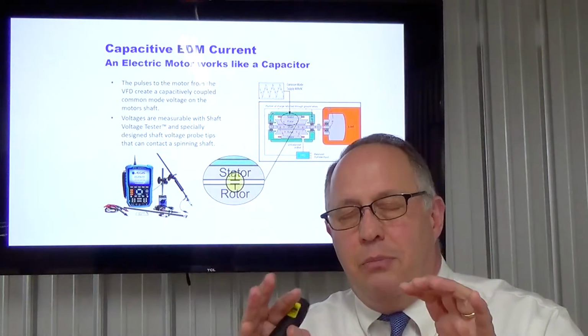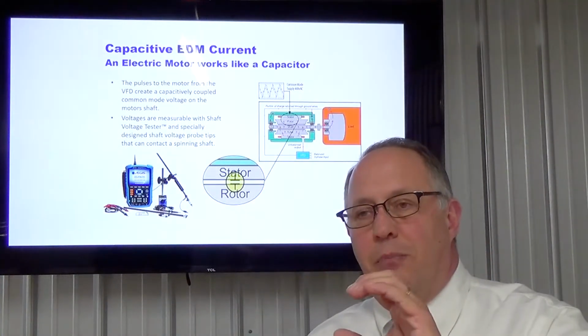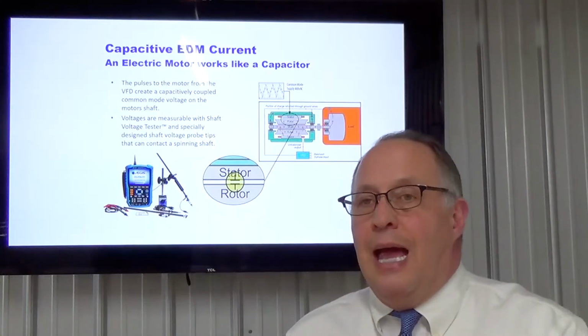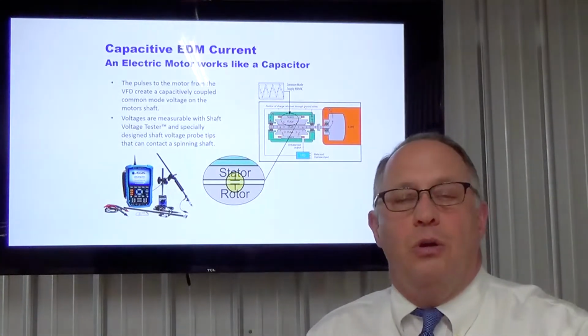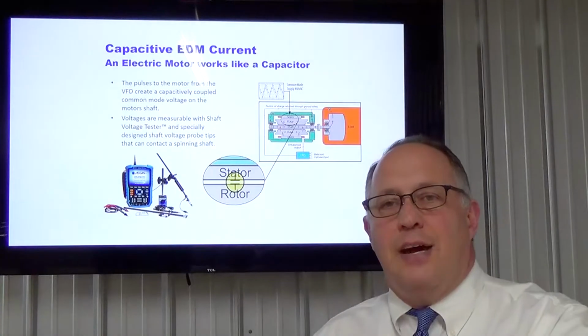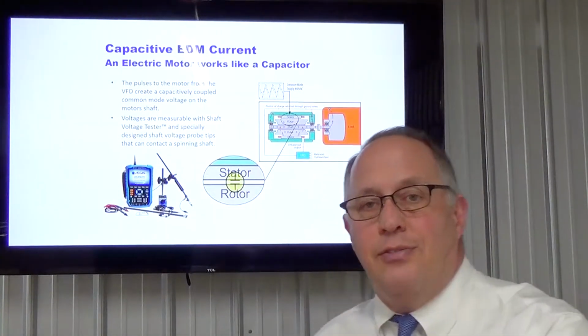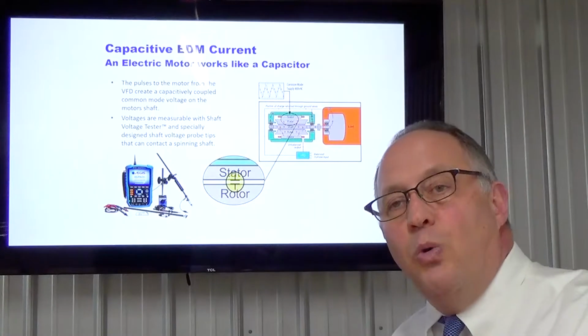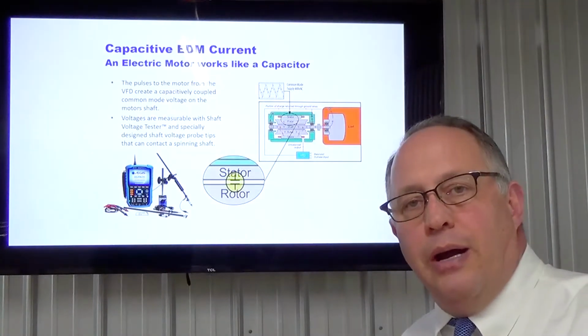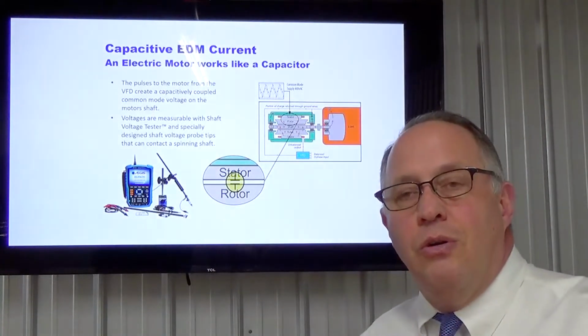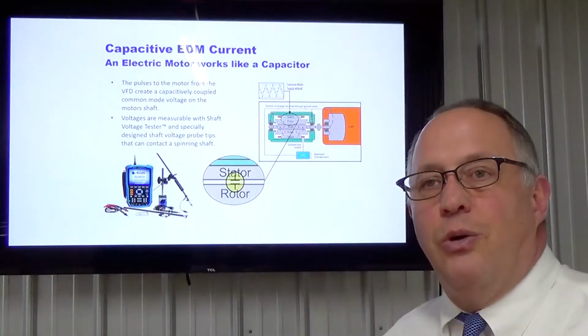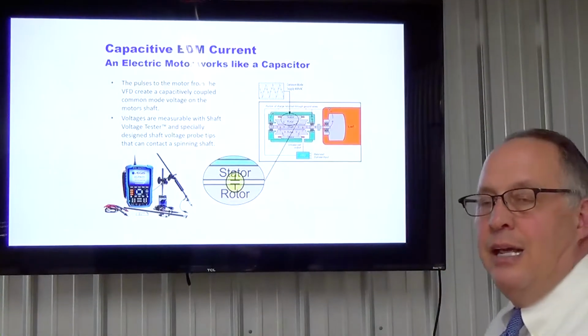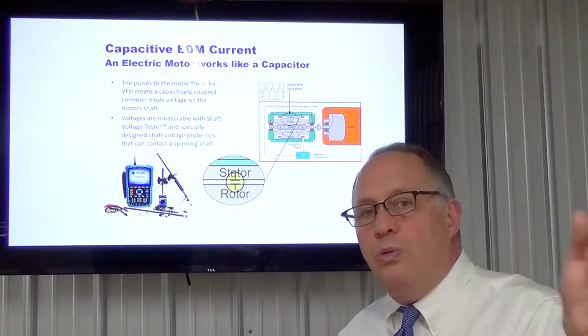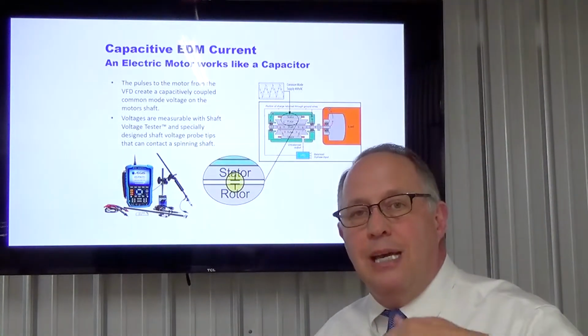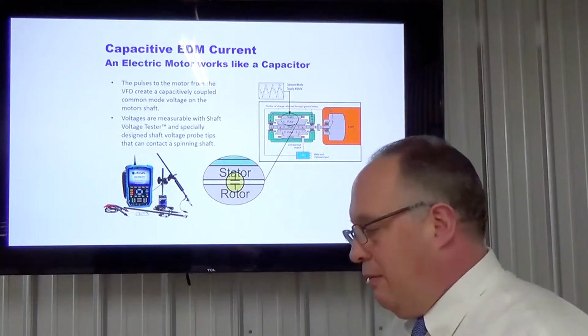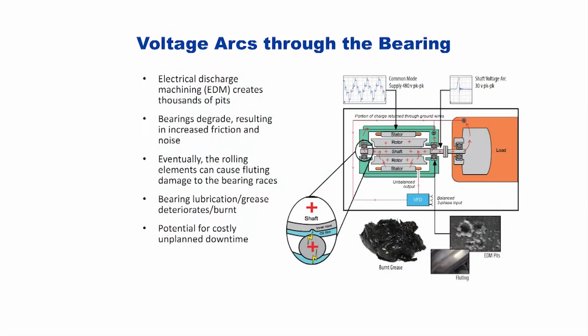So let me demonstrate this from an information standpoint. The shaft is turning at whatever frequency you need to meet the load requirements. If you go from the shaft to the motor housing ground or to a properly grounded system, you can measure voltages being induced on that shaft through this capacitive effect. Now, those voltages want to get to zero. They want to get back and dissipate. But how does that happen?